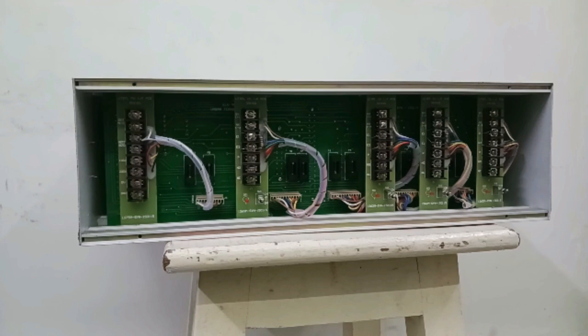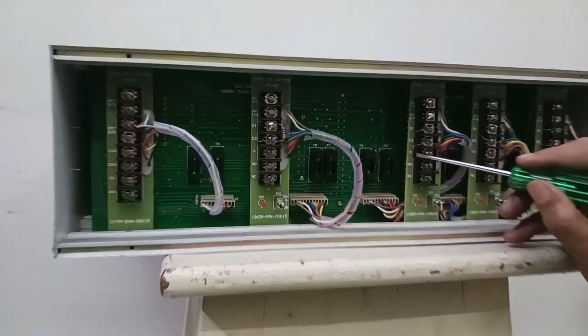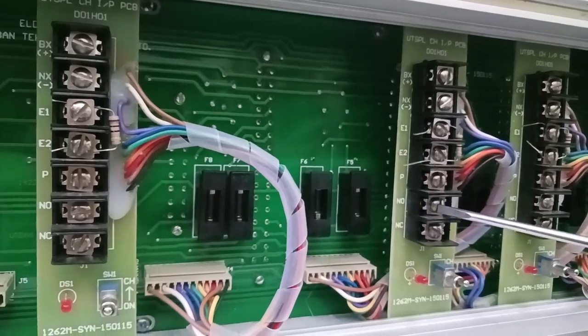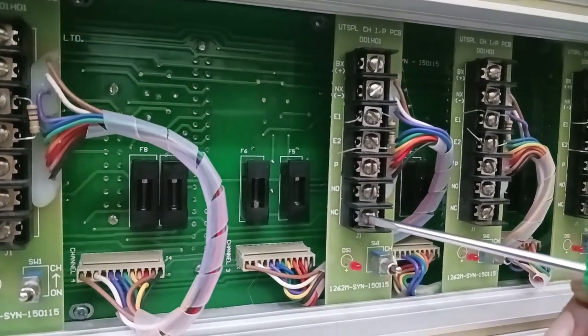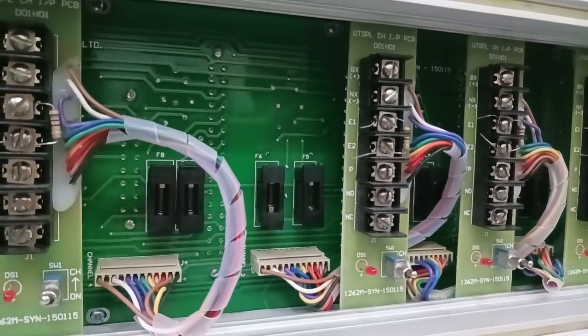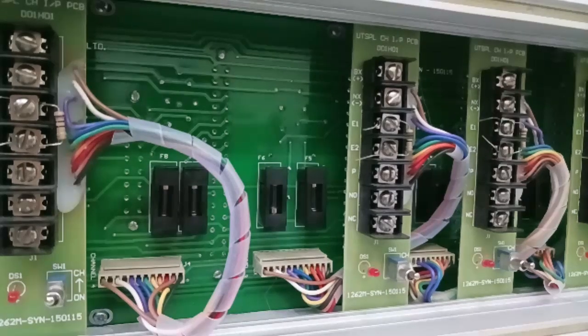You can get the alarm information from individual channels through potential free contacts. These contacts are available on the 4 connecting terminal sets on the back panel. The P-marked point is common, the NO point is normally open and the NC point is normally closed contacts of the relay. During OK condition, the relay is in picked up mode. When alarm appears, the relay is set to released mode. These contacts can be successfully used by data logger to identify exact incident moment of the failure.